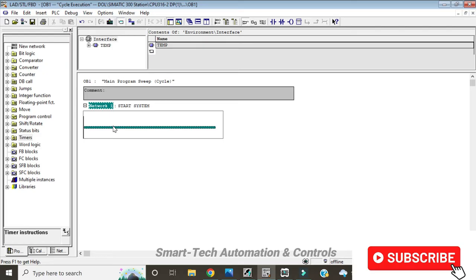I will then introduce a normally open contact, which will be our Start System button. Then a normally closed contact, which will be our stop button, and then a coil, which will be the start memory. Then I'll introduce a hold on circuit, with a normally open contact, because our start button will be a push button.